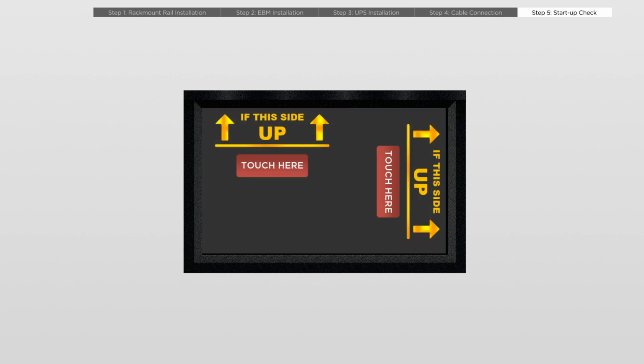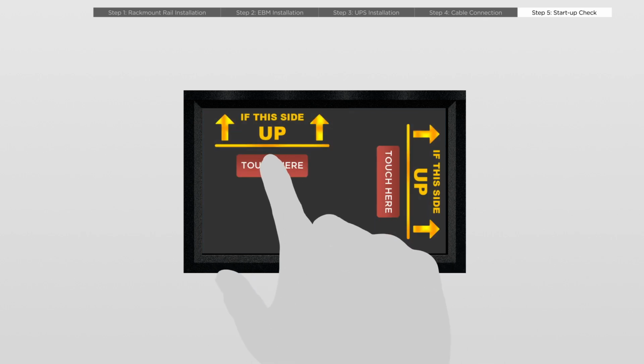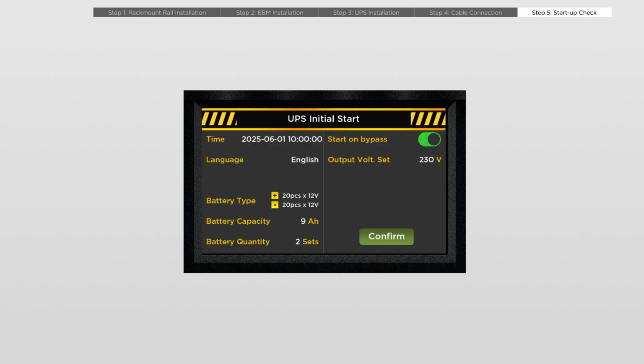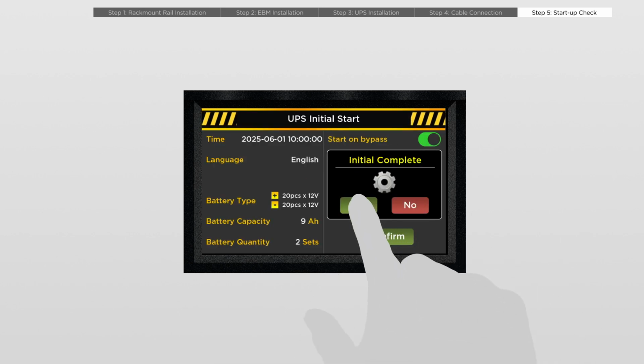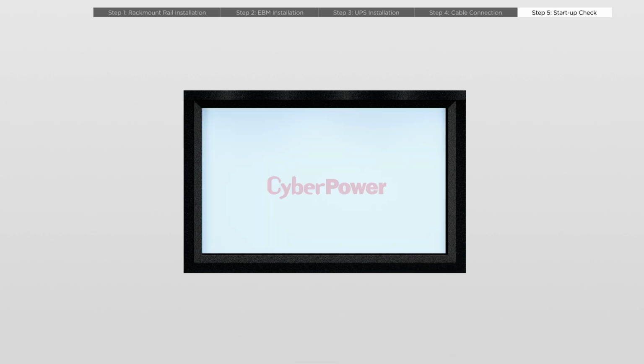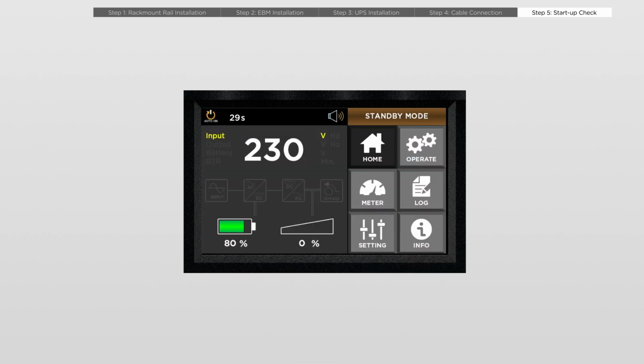Turn on the external circuit breaker and the UPS begins initializing. Select the rack mount display orientation. Complete the initial settings by configuring the parameters. The UPS will run self-tests, which may take a few minutes, then transfer to line mode when ready for use. For optional inspection, verify that the UPS switches to battery mode by turning off the input circuit breaker.